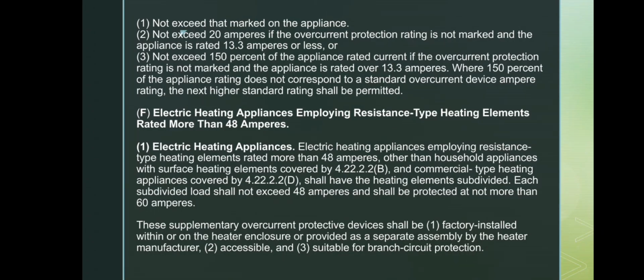And now for the rules on overcurrent protection for a single non-motor operated appliance. First, the overcurrent device must not exceed the rating marked on the appliance. If the appliance has no marked rating and its load is 13.3 amperes or less, the overcurrent protection must not exceed 20 amperes. If the appliance is over 13.3 amperes and still has no marked rating, the protection can be up to 150% of the appliance rated current. And if the 150% doesn't match a standard device rating, we are allowed to use the next higher standard rating.